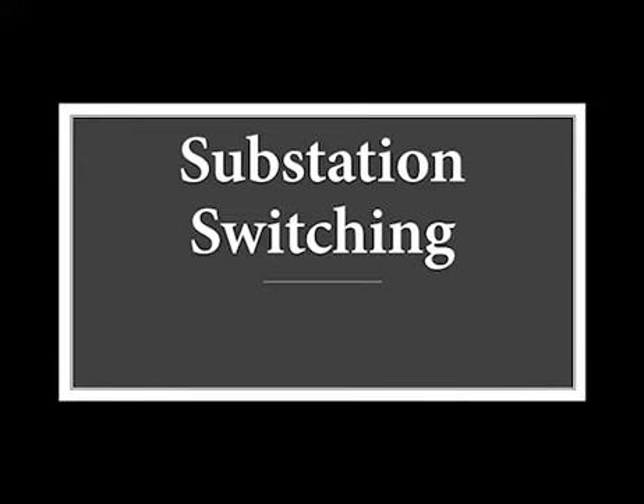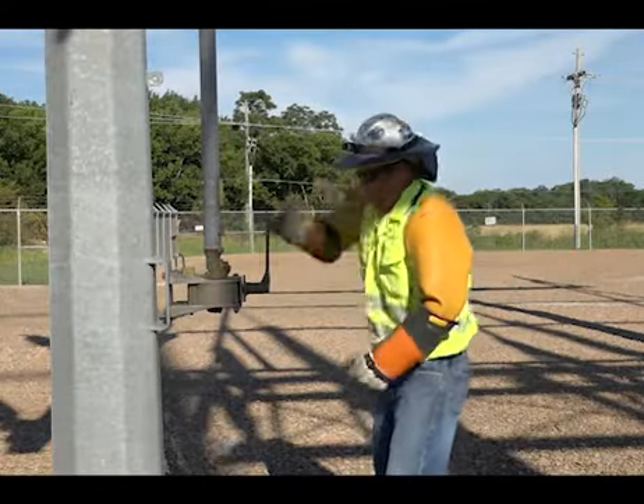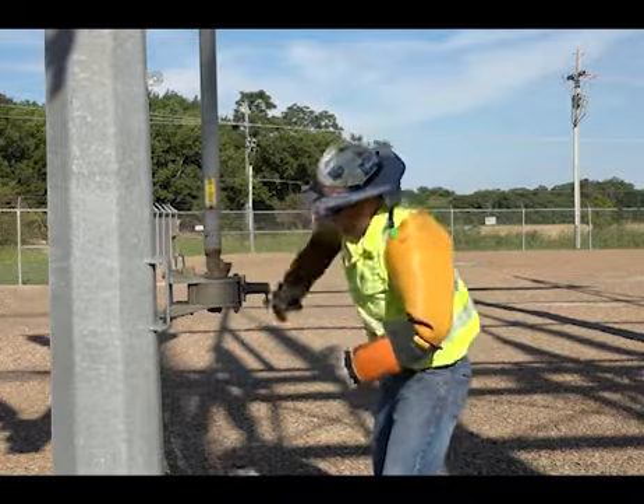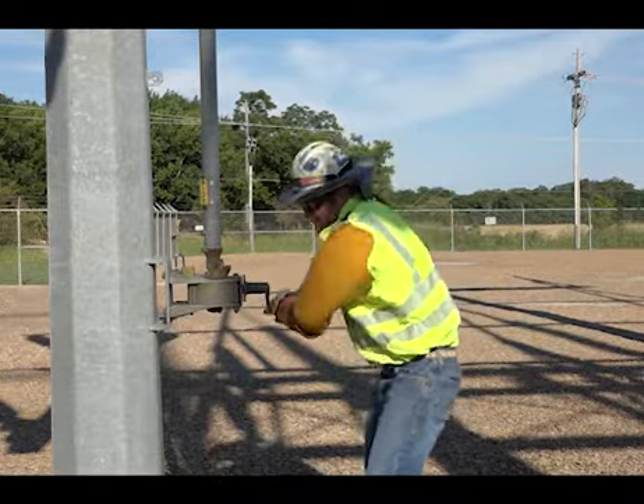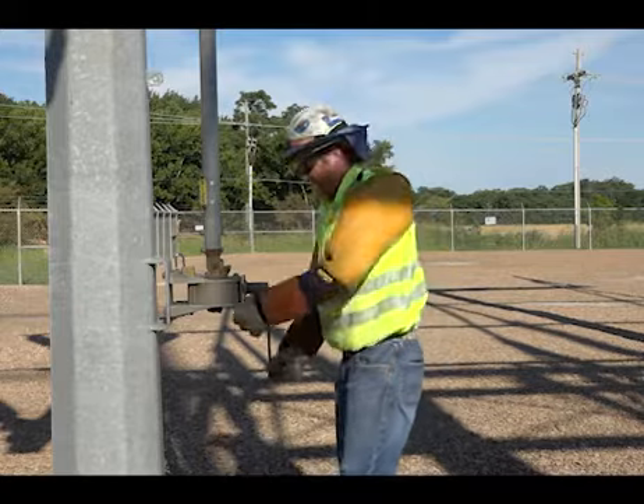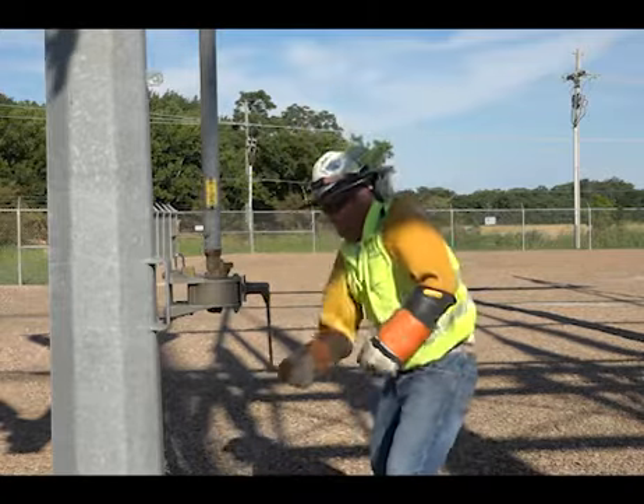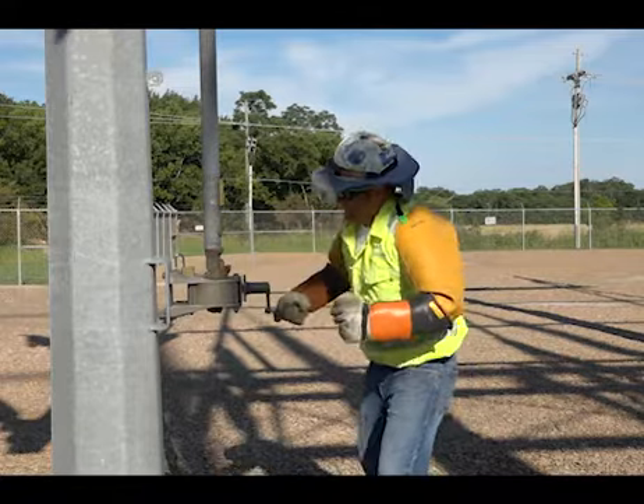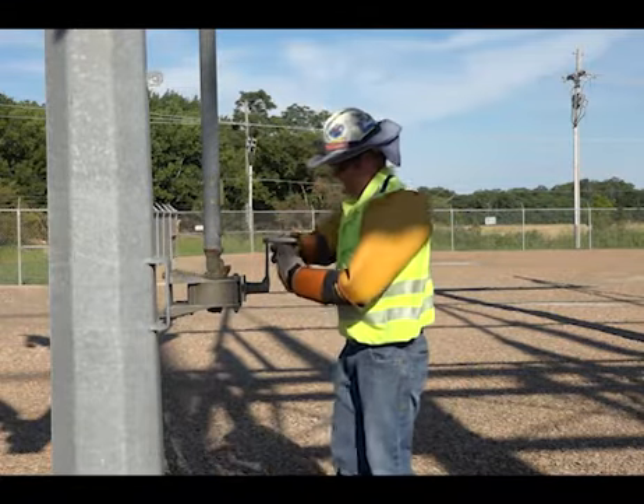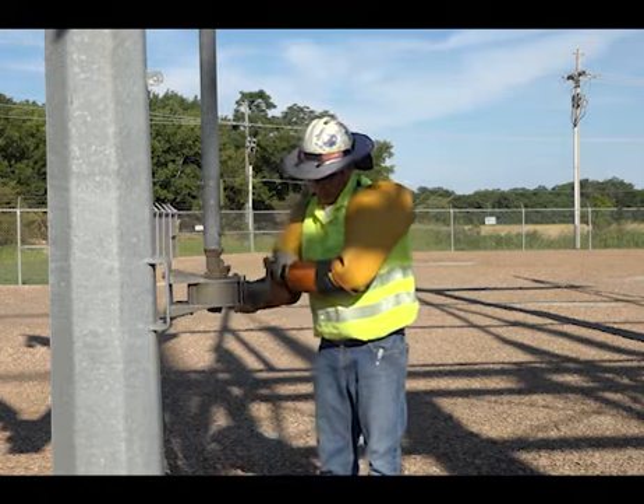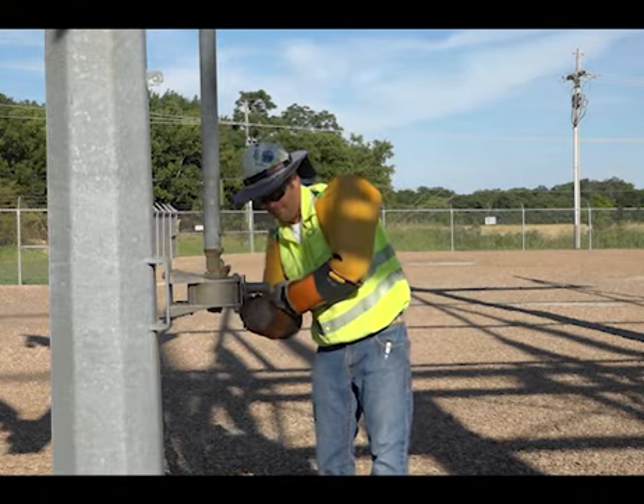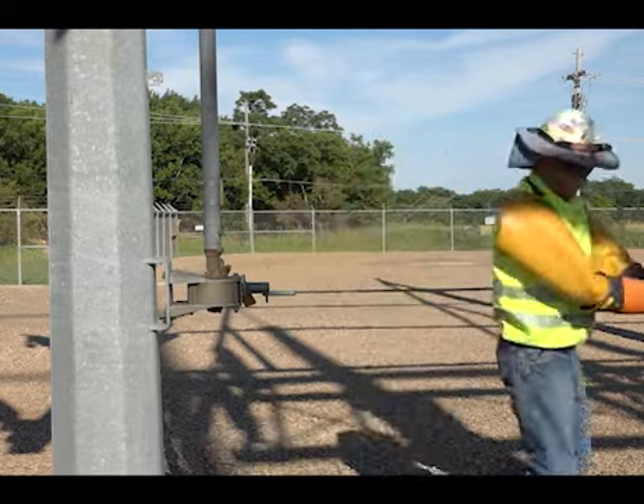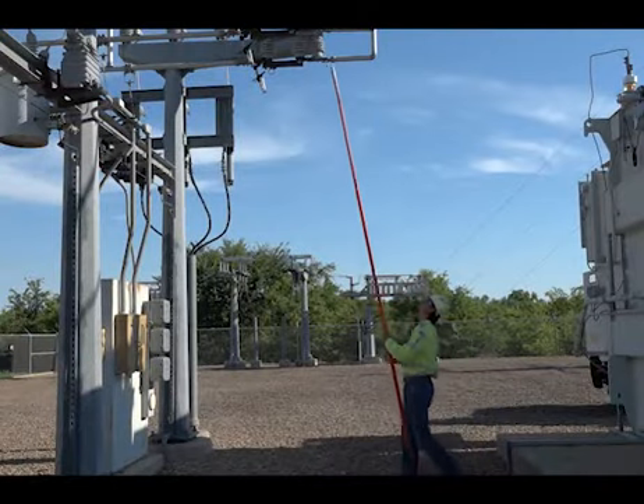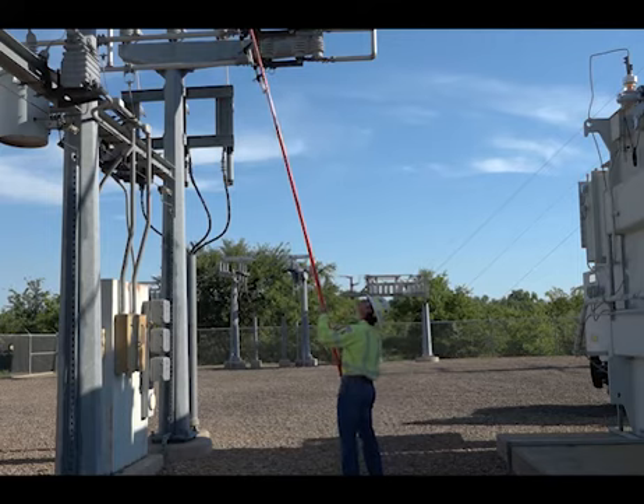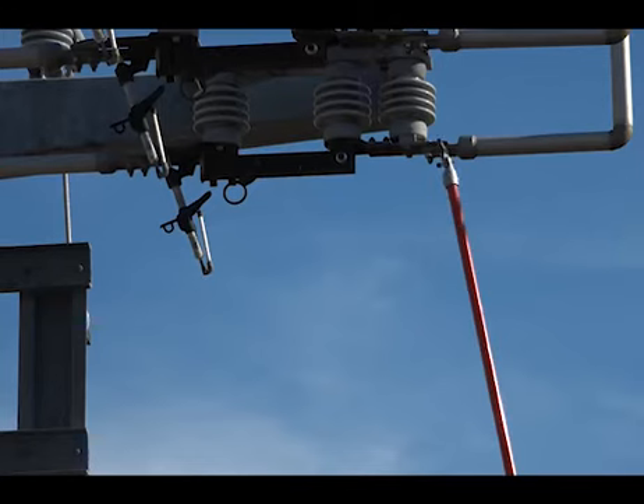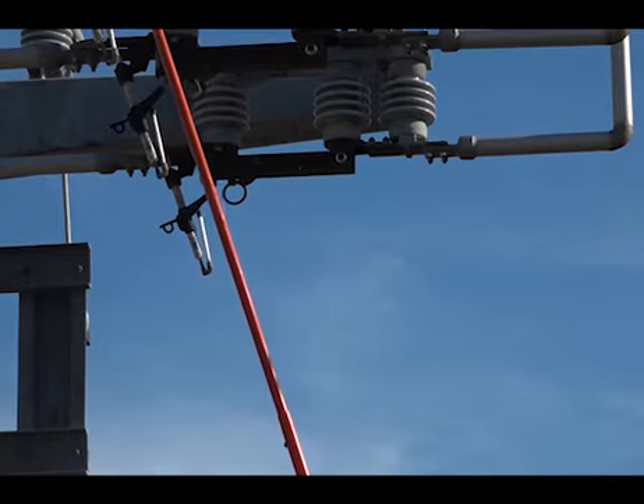Substation switching. It is critical to understand how to take the system out of service and how to restore the system back to service. Always use an OMPA-approved switching procedure. Know and understand lockout-tagout procedures and how to use them. Know and understand the equipment you will be operating during any switching procedure. Use rubber gloves when operating switch handles. Use a properly rated and tested hot stick to operate any devices that are energized, such as cutouts, air switches, etc.